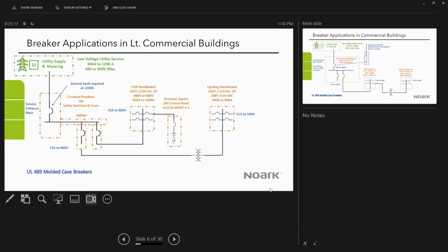service. And the service comes into what's called a service entrance main device. So this is a circuit breaker. It could be a fusible switch that is approved for use as the service entrance main. And that's approved based on its design under the standards, but also by the local utility who is connecting to that device. Power is then distributed through a splitter, and then from the splitter, you can take off a number of smaller breakers. So typically, you wouldn't see in this kind of an application a main breaker above 1200 amps. And then the feeders that come off below it are anywhere from 15 to 800 amps typically.